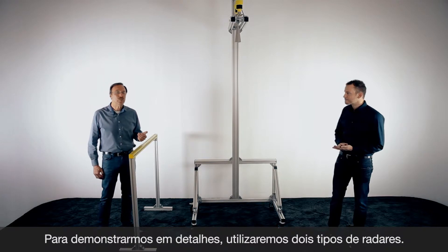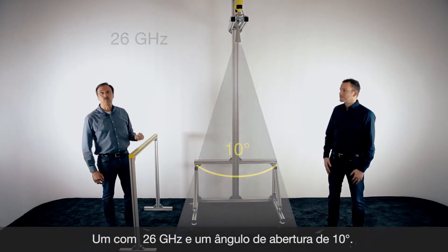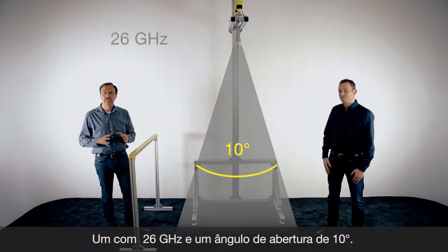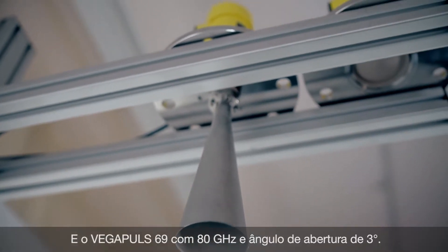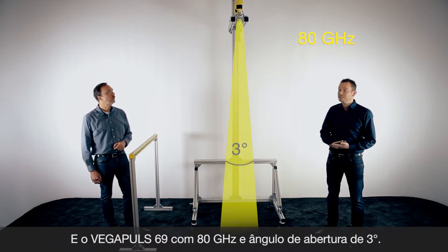To show you some details, we have installed two radar sensors on top here. One is working with 26 gigahertz and we use a wall antenna with a focusing of approximately 10 degrees. Directly in front we have installed a VEGAPULS 69, our radar sensor for bulk solids with 80 gigahertz and a beam angle of only three degrees.